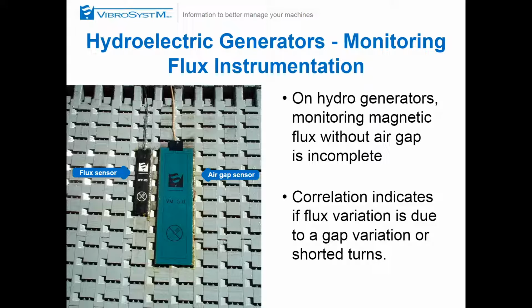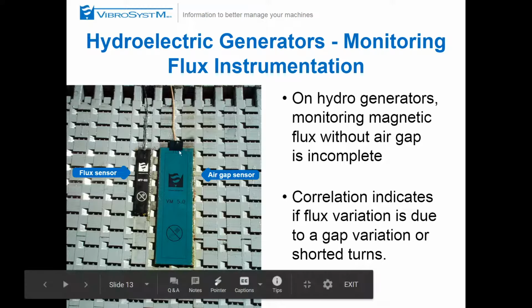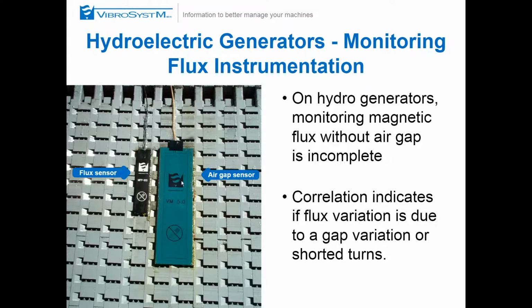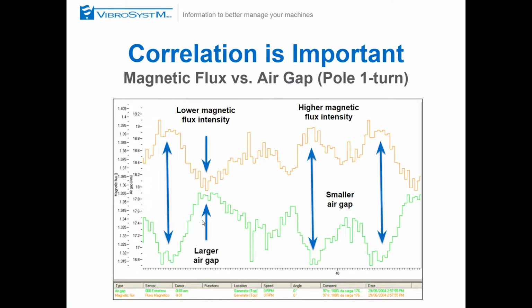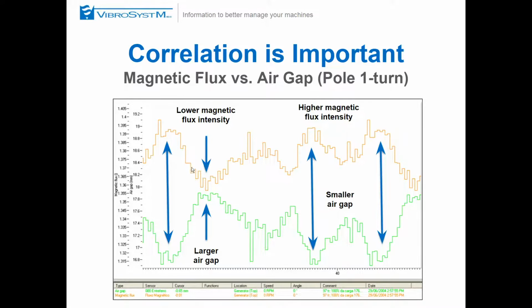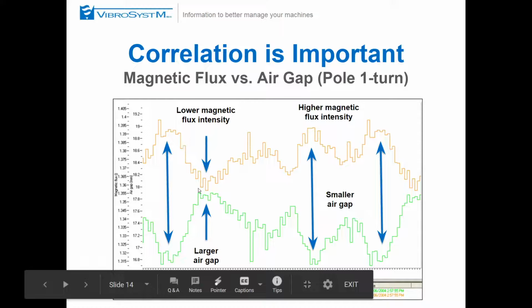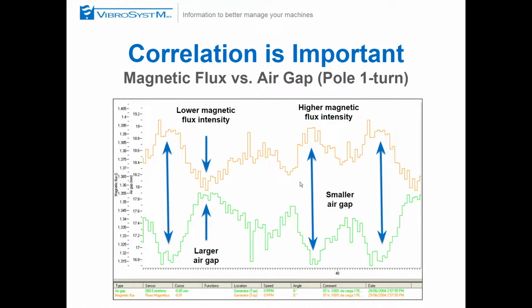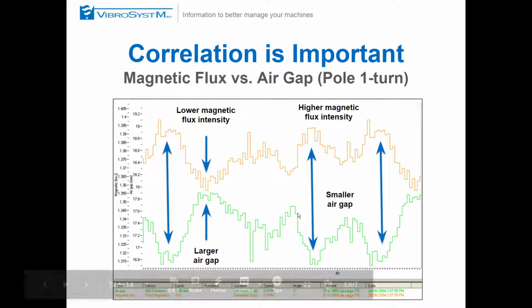It's not a factor. However, you can have serious issues with shorted turns, and we have this sensor as a solution, and we put it next to an air gap sensor because the correlation between the two will tell us if there's a shorted turn or not. For example, you see the air gap profile here of that adjacent air gap sensor, and you can see that the magnetic flux is inversely proportional. So the smaller the air gap, the higher the magnetic field intensity. The larger the air gap, the lower the magnetic field intensity. And if you have any serious dip in the magnetic profile that is not corroborated by a greater air gap, then it means you have a shorted turn issue on that pole. Otherwise, they should all basically match. You can see how this shape is inversely proportional to this.